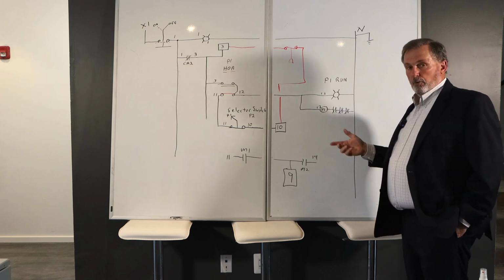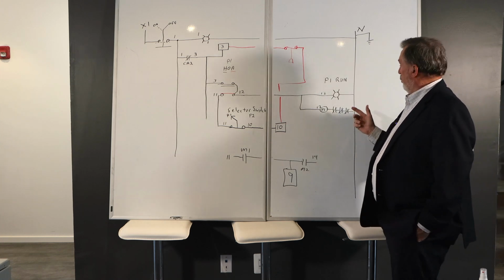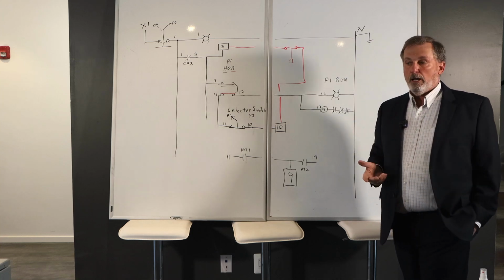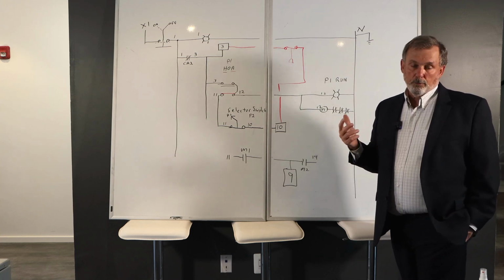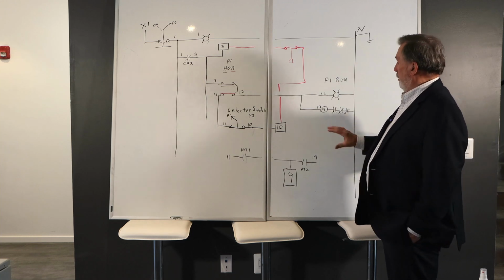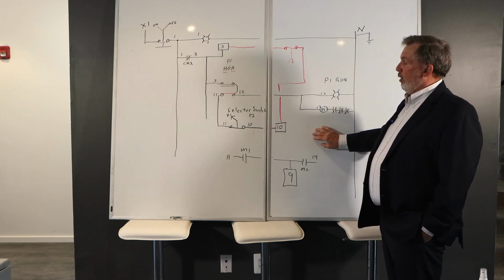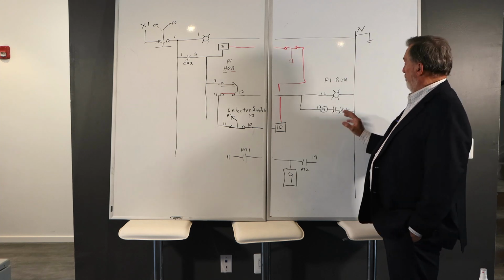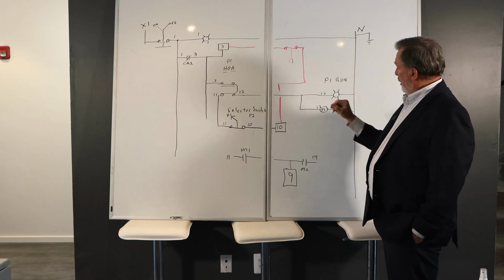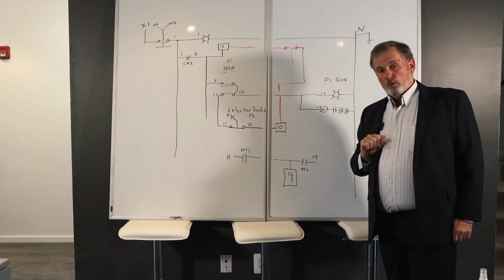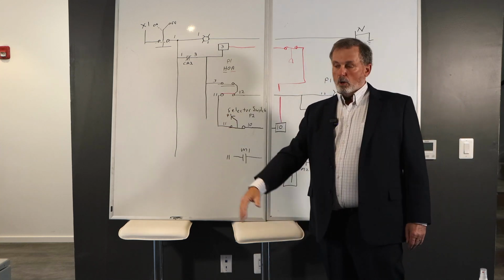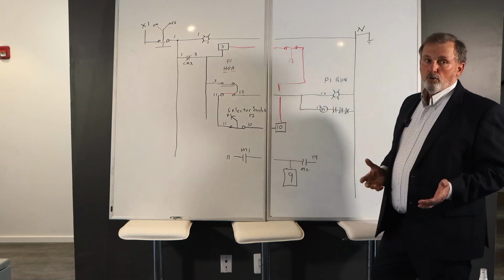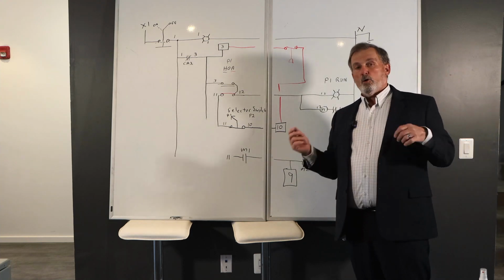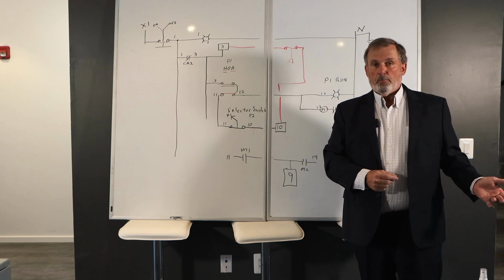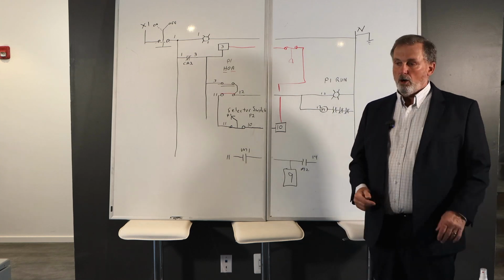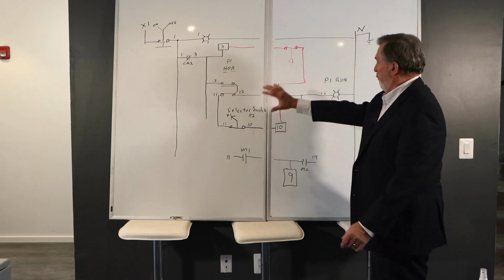Okay, now there's other circuitry involved here. We're going to have some alarm contacts. The pump's going to alternate automatically and so on. But this is a typical hand-off-auto operation to run a pump. Now bear in mind that the pump motor, once again, the pump is running on 480 volts. There's no 480 shown here anywhere. Everything in here is just 120 volt control that's telling the motor when to run and when to shut off. Okay, it's also telling us if we have high level alarm and so forth. Okay, but there's no 480 here whatsoever.